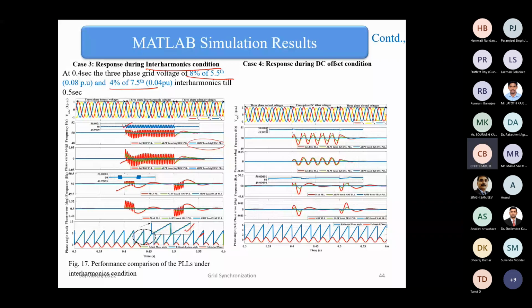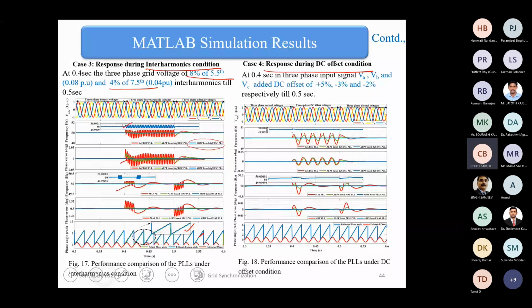And this is the response during DC offset. During DC offset, we are injecting plus 5% of a DC component in the A phase, minus 3% of a DC component in the B phase, and minus 2% of a DC component in the C phase, until 0.5 seconds. Now you see the proposed PLL in blue is exactly tracking the fundamental 50 Hz. There is no phase error. There is no frequency error. It is completely following the reference of 50 Hz, and it is exactly tracking the value of the fundamental phase during DC offset.